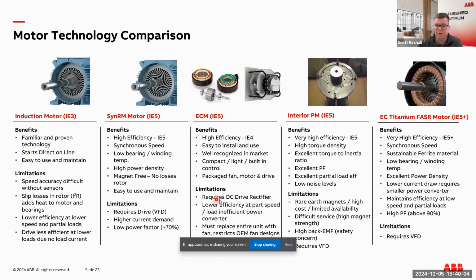We've got some of the benefits and limitations across these. I won't go into loads of detail, but it's there for reference. The main point is all the technology is pushing for higher IE ratings, and this is a good starting point for your system. Generally, an IE5 compared to an IE4 would be more efficient, but you've got to check on the operation. If the IE5 is operating badly and the IE4 is optimized, it could be close. So it's not a way of determining efficiency just off the top of your hat.